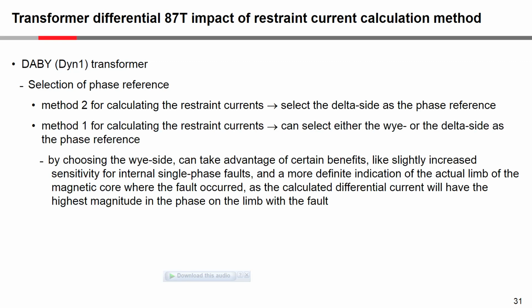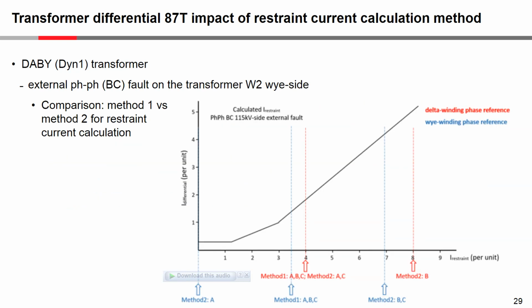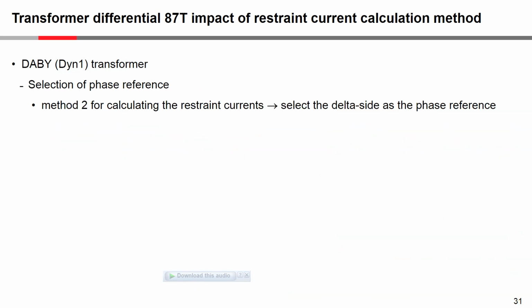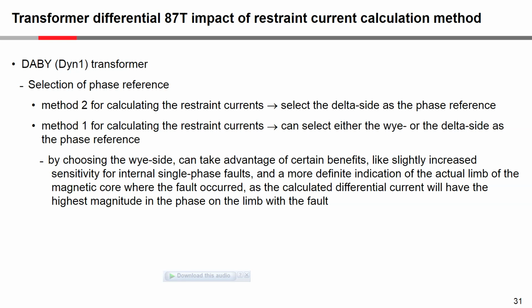If we use method 1 for calculating the restraint currents, then we can select either the Y or the delta side as the phase reference, because again, if we go back here, the Y side is the phase reference. So if we're calculating the restraint currents with method 1, then we would have sufficient restraint current. So with method 1, we can select either the Y or the delta side as the phase reference. All right.